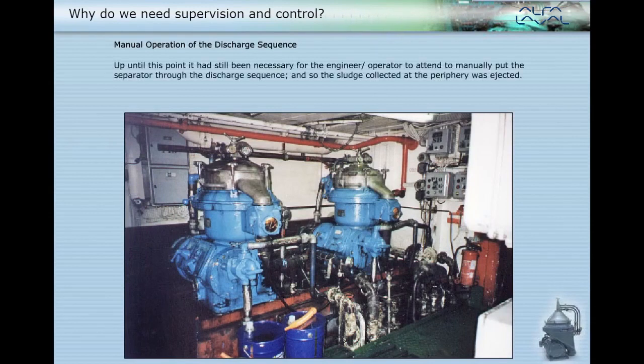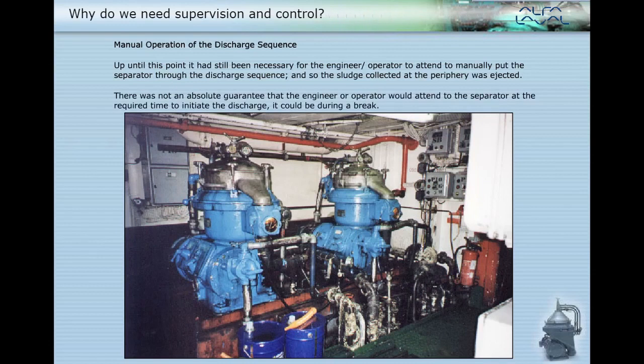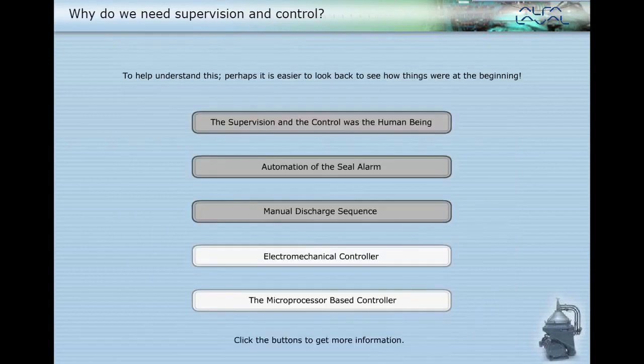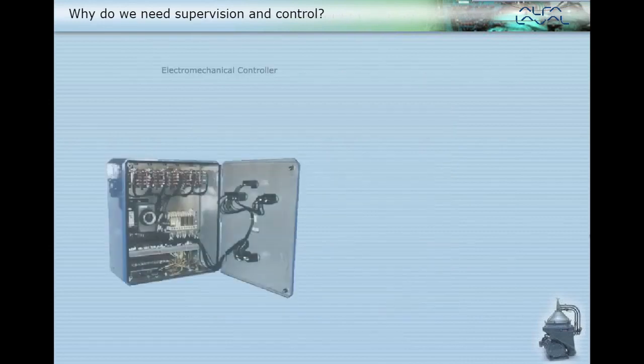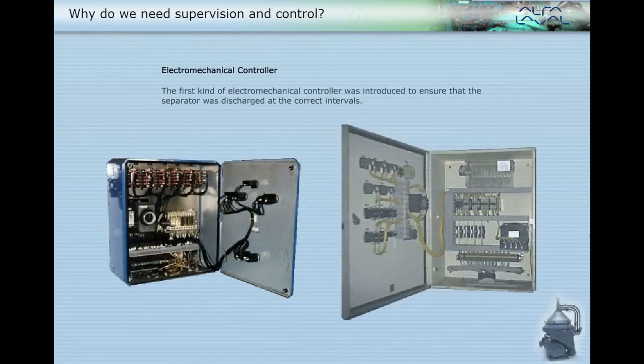Up until this point, it had still been necessary for the engineer or operator to attend, to manually put the separator through the discharge sequence, and so the sludge collected at the periphery was ejected. There was not an absolute guarantee that the engineer or operator would attend to the separator at the required time to initiate the discharge. It could be during a break. The first kind of electromechanical controller was introduced to ensure that the separator was discharged at the correct intervals.